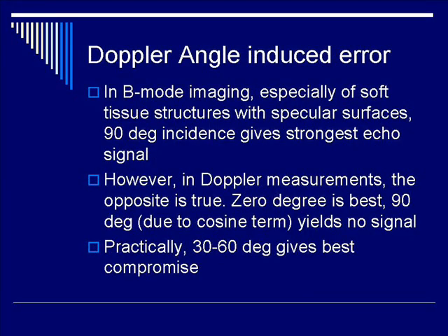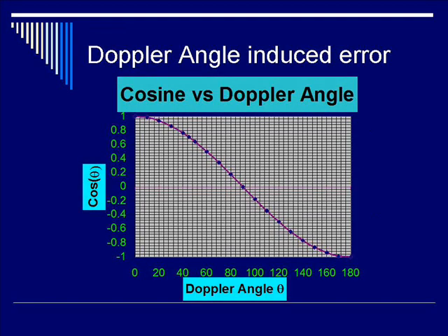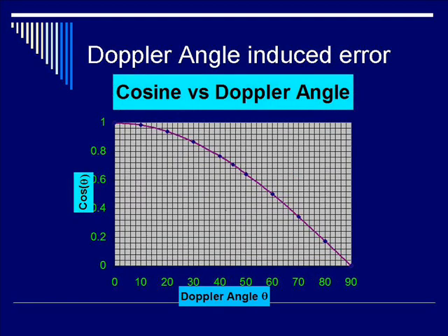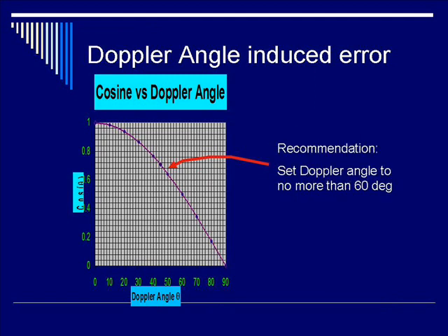Unlike B-mode imaging, in which 90 degrees gives you the best signal strength, in Doppler measurement if you measure at 90 degrees you'll get zero signal due to the cosine term. Therefore, for the best compromise, 30 to 60 degrees is best. The cosine angle curve shows a steep drop-off in signal when you approach the 50-degree angle mark, so for practical purposes you want to measure at no more than 60 degrees.